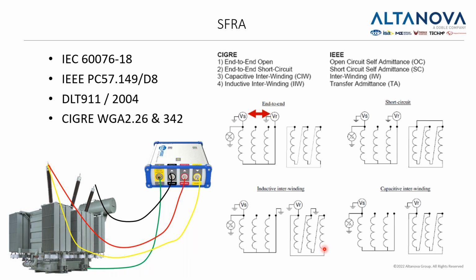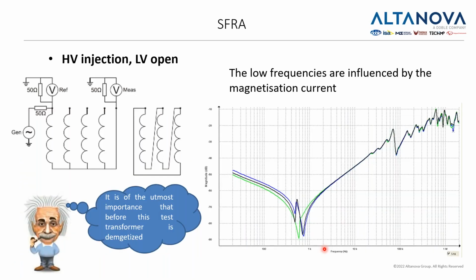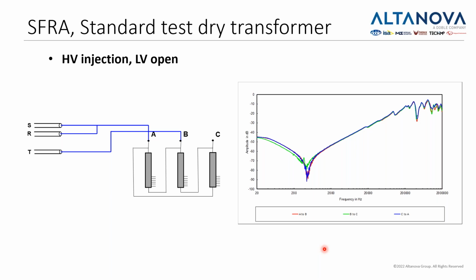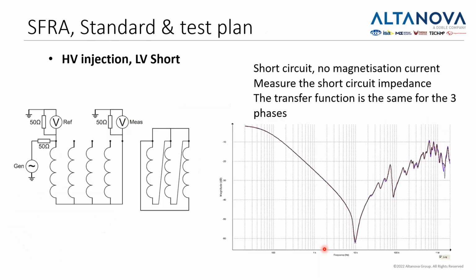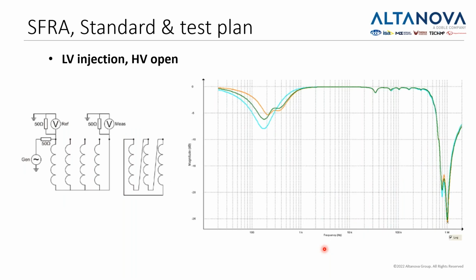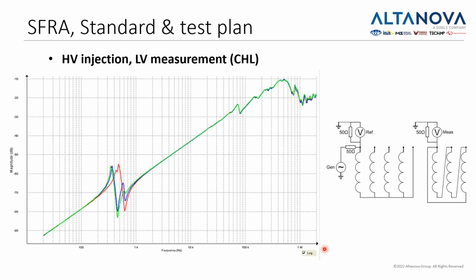Now, there are a few standards how to do this, and regretfully, we don't have time for that, so I'm just going to go quickly through this, but I'm just going to mention once again that before we do this test, we need to demagnetize the transformer. That means that if we have done the test of winding resistance before this, and then we do the sweep frequency response analysis, we will not get good results. So we need to demagnetize our transformer. And then there are ways how to do this test. So high voltage injection, low voltage side open, or high voltage injection, low voltage side shorted, and then low voltage injection, high voltage side open, and high voltage injections and measurement on the low voltage side.